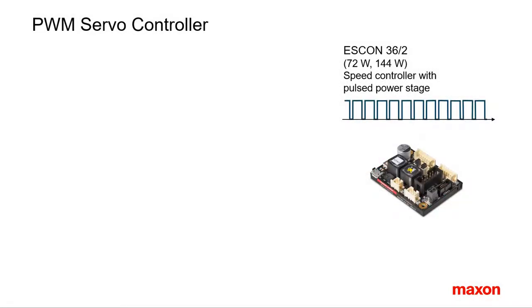Starting point is a look at the pulsed power stage of modern controllers. Fast transistors are used to switch a supply voltage rapidly between maximum and zero volt. In this way, the transistors work efficiently with low losses because they are either fully conductive with low resistance or fully closed with zero current. Consequently, the thermal management of motor controllers is much easier and the controller can be made smaller.